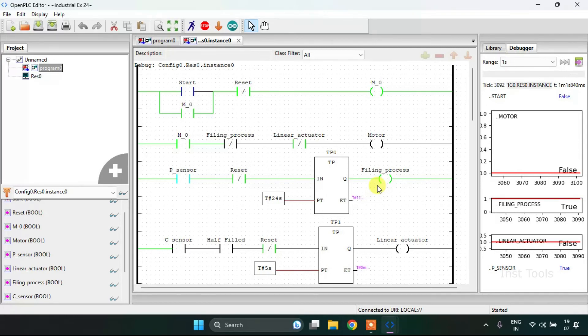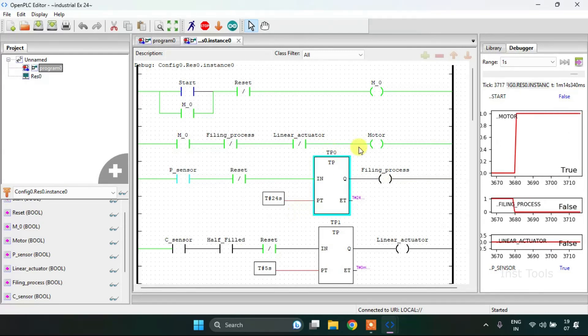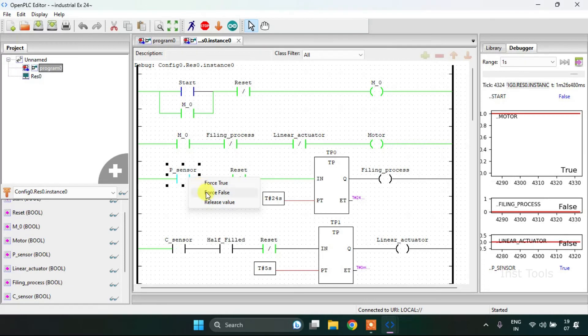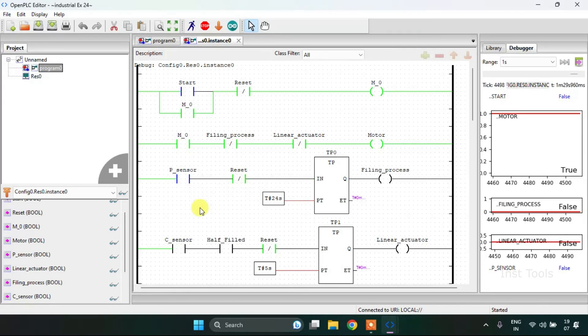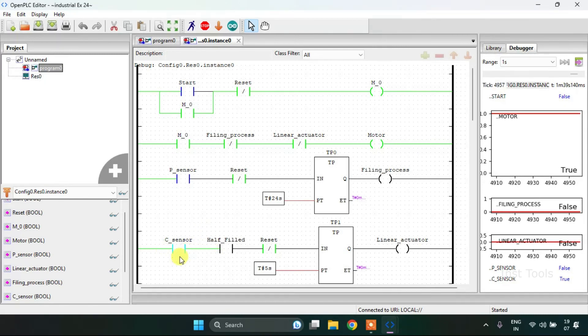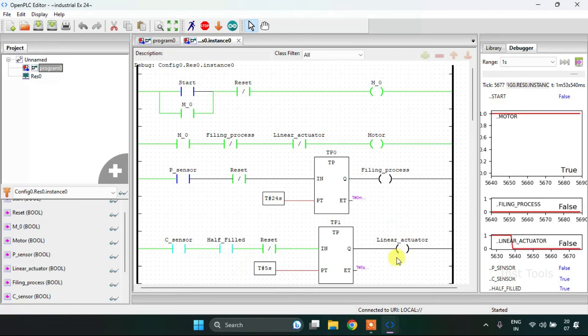Then the filling process starts — 12 bottles are placed inside the box, which is happening over 24 seconds. After 24 seconds the filling process goes false and the motor starts running again, which in turn deactivates the proximity sensor. Then there comes a point when the camera-based sensor will sense the box and check if it is half filled or fully filled. If it is half filled, the linear actuator will place the half-filled box onto another conveyor and the motor will start running again.